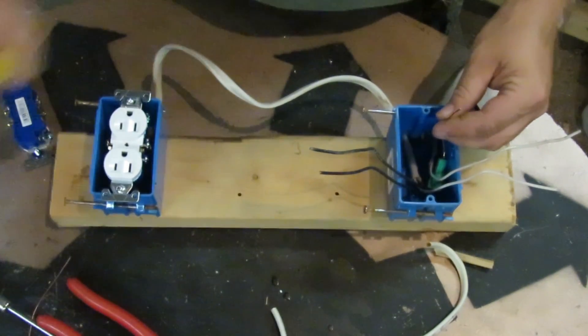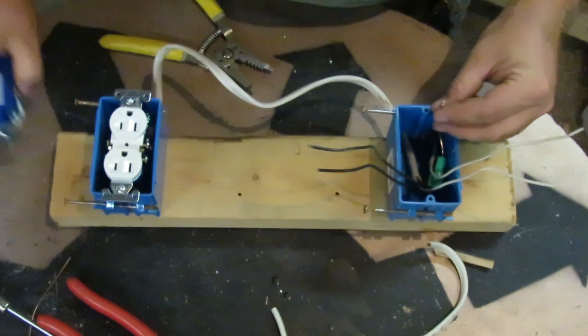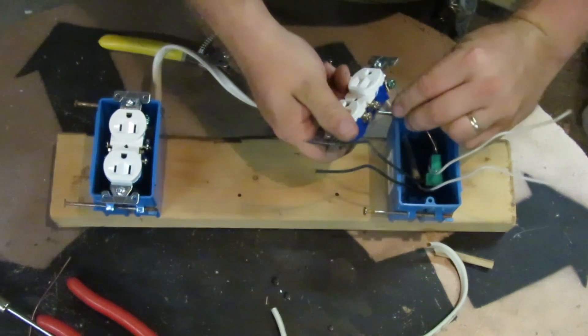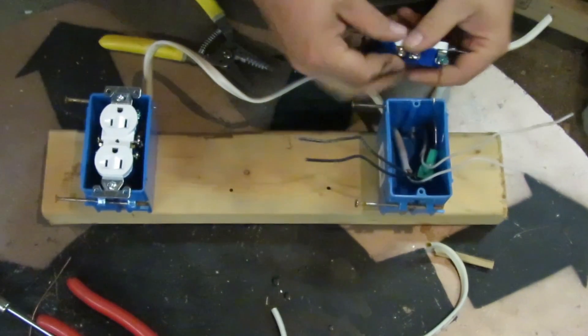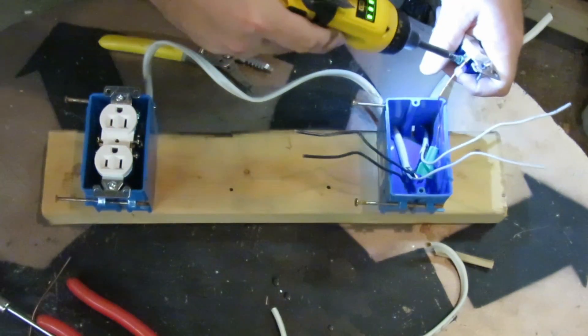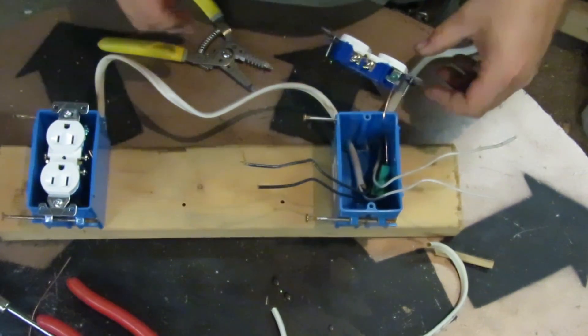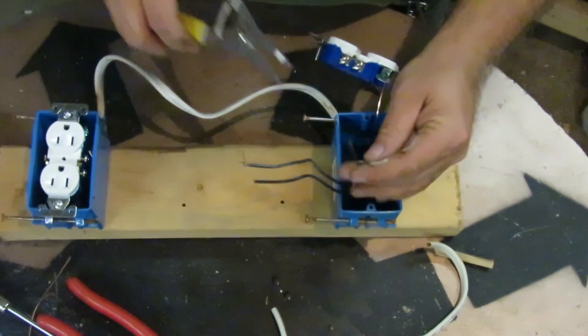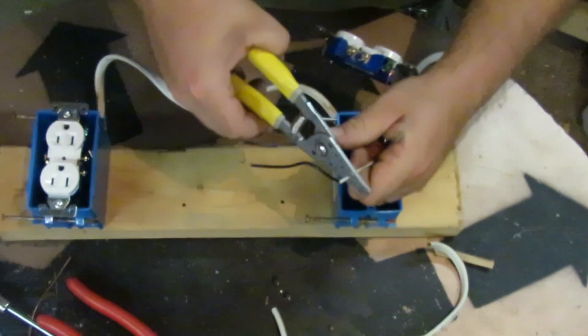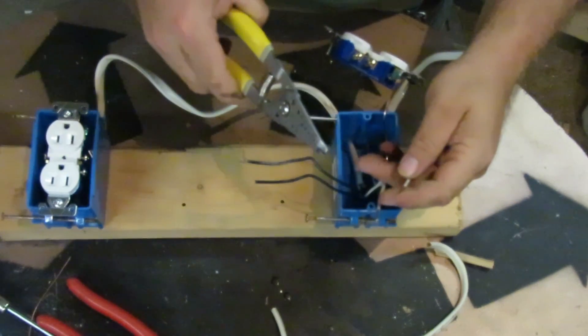Well, hooking up a receptacle with two or more sets of wires is about the same. You hook your ground wire and tighten that down. And then you're going to strip off your neutral wires. And always remember that your neutral goes on the silver screws. It's easy to remember. The white wires go with the white screws.